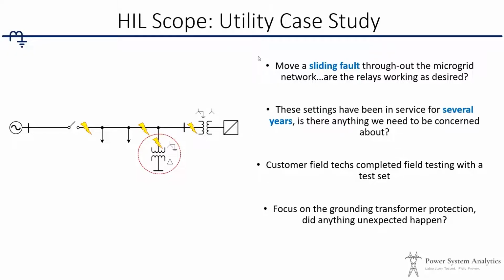Various fault types were considered: single line to ground, phase to phase, etc. These settings had been in service for several years, and the utility wanted to know if there was anything they needed to be overly concerned about. One big thing was that the field technicians had been involved with testing the relaying out in the field. They felt pretty comfortable with it. It had passed a lot of the tests they had thrown at it. They sent us copies of those reports, and we took that data and rolled it back into a study.